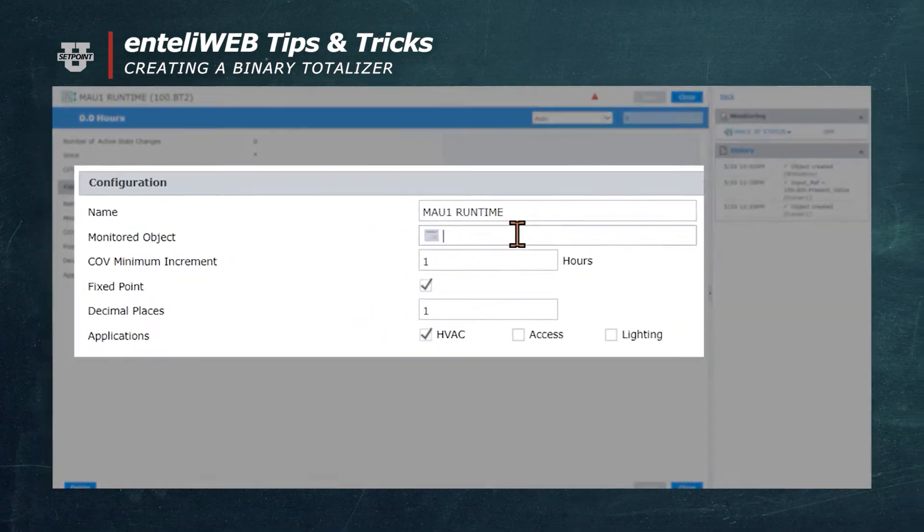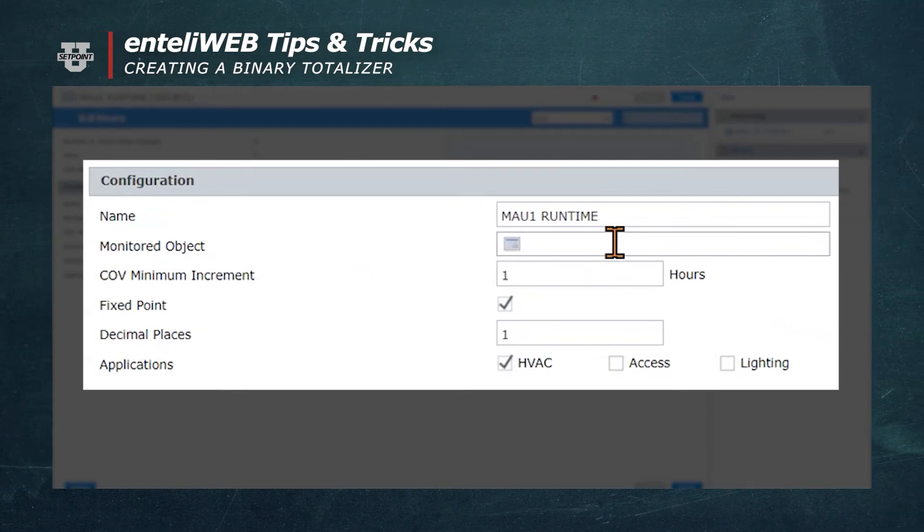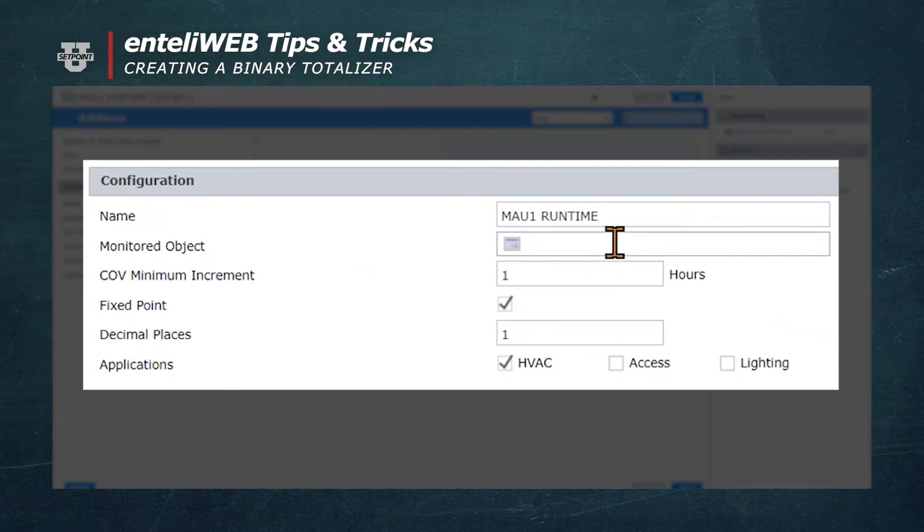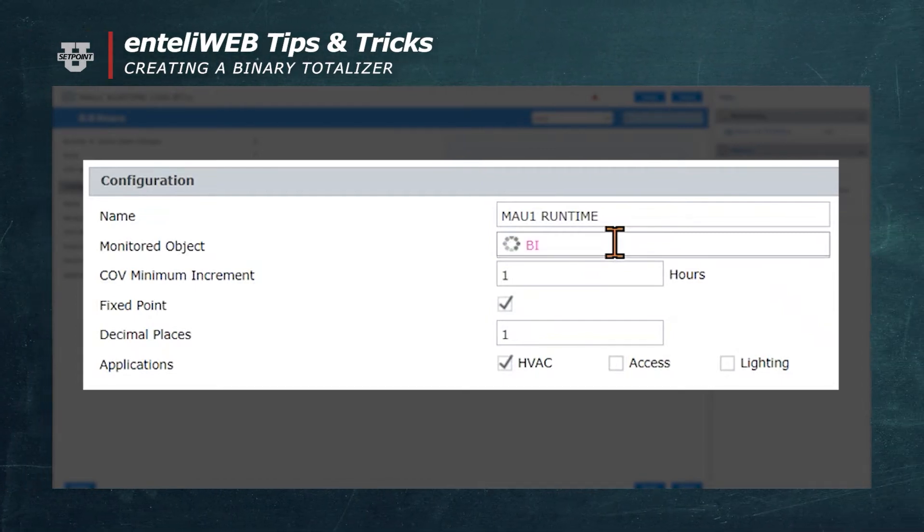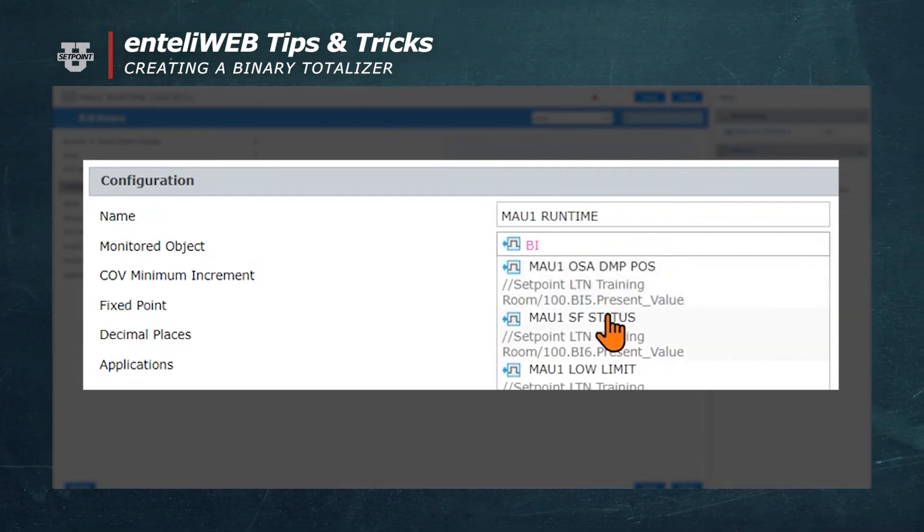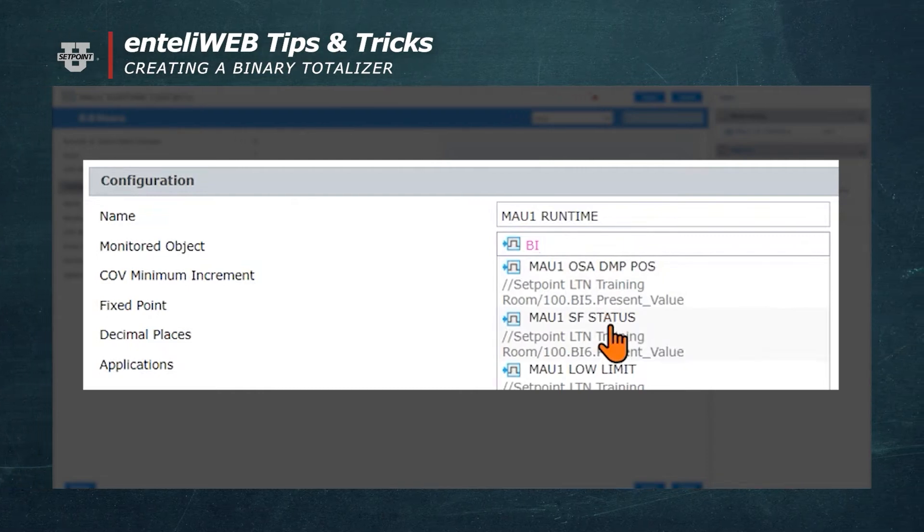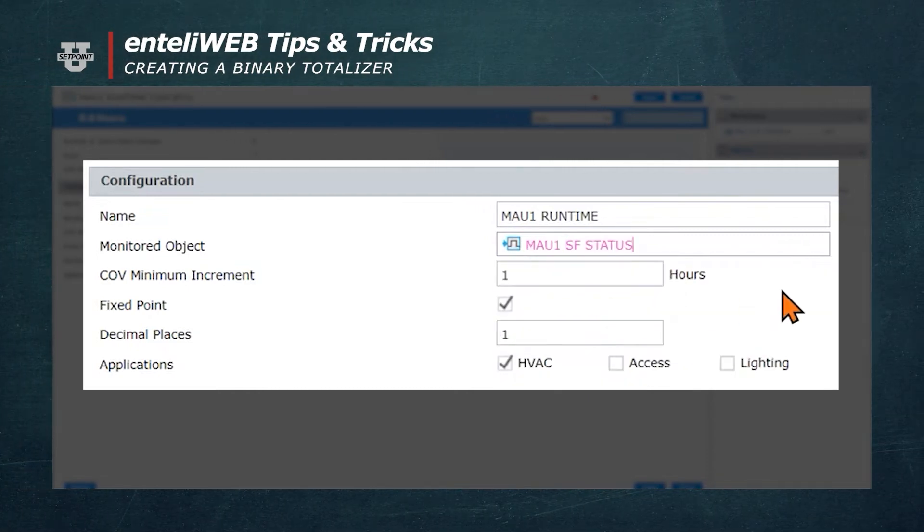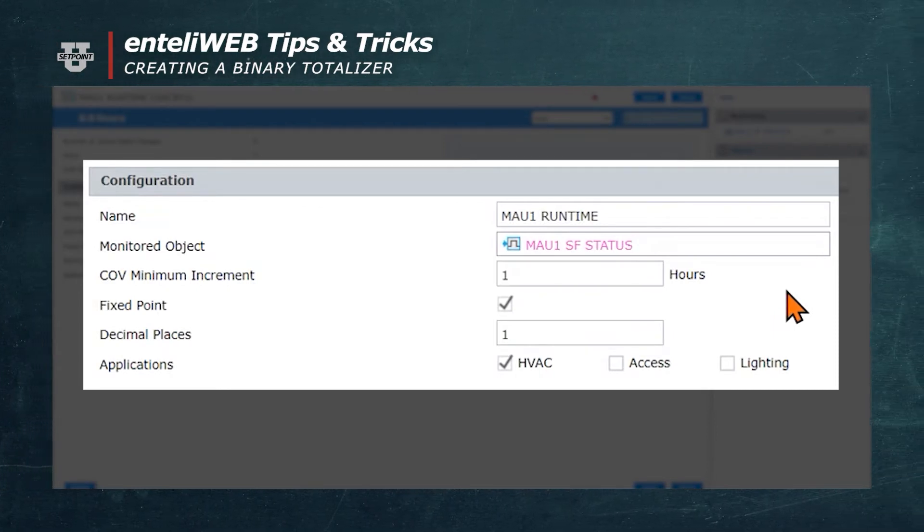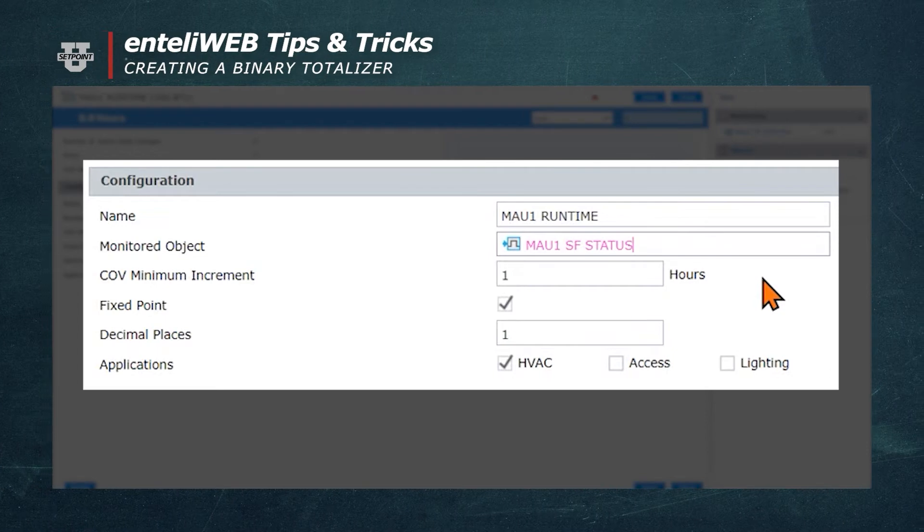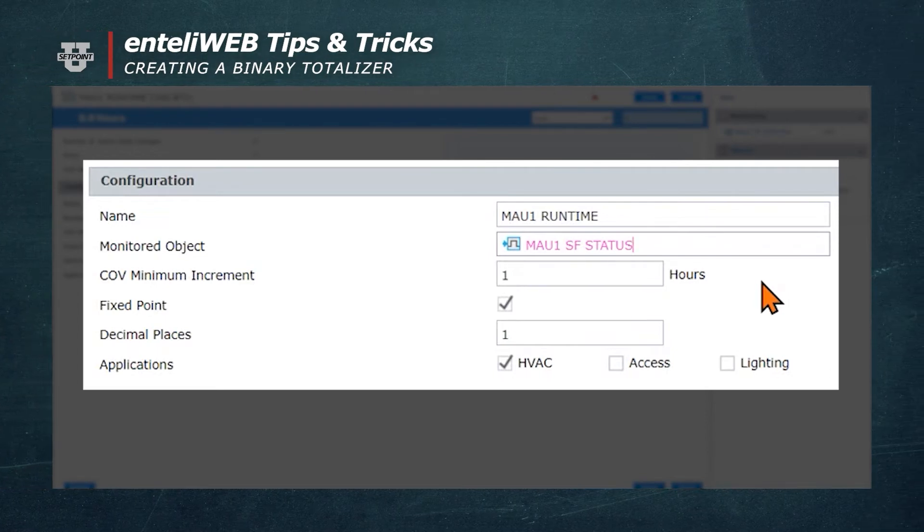The BT window pops up and it will ask us for the monitored object. This is where we'll calculate for how long this object has been on or off. We'll use the status because we want to be able to calculate the runtime, regardless of whether the DDC system turns it off or on. If somebody manually turns it on in the field, we would still get a status, so we can make sure that we document the runtime there as well.